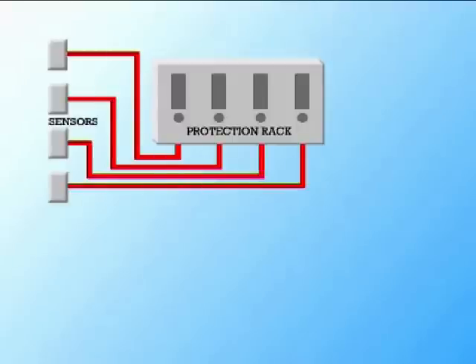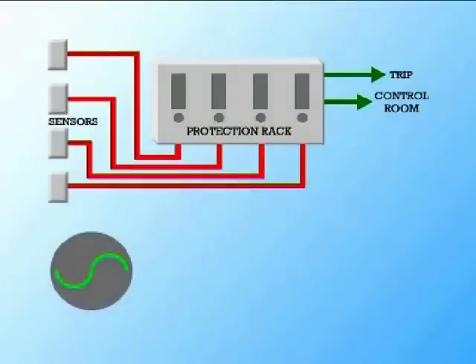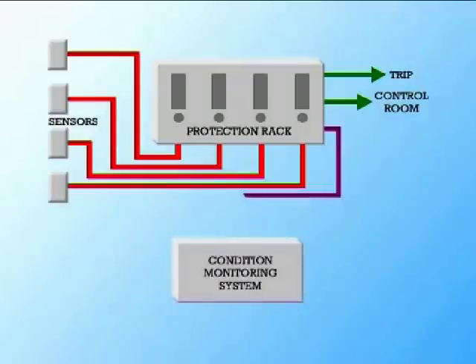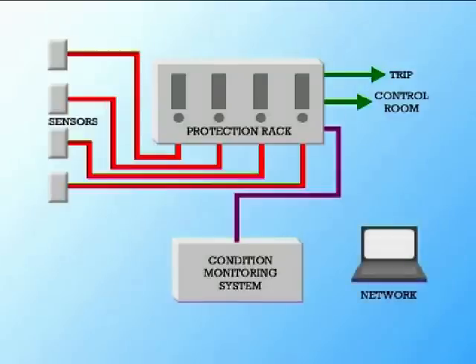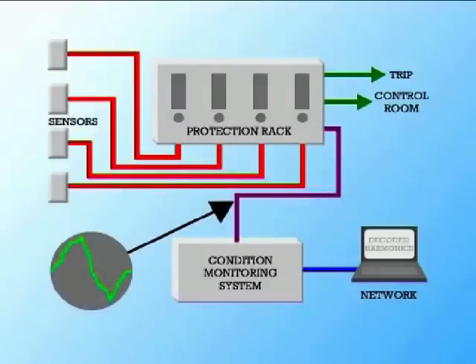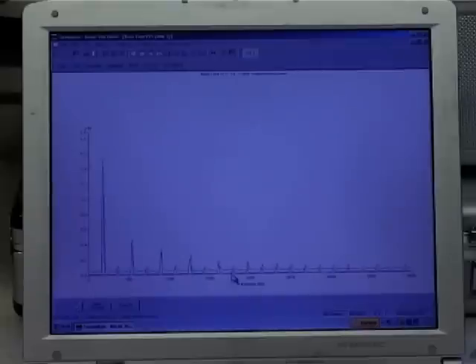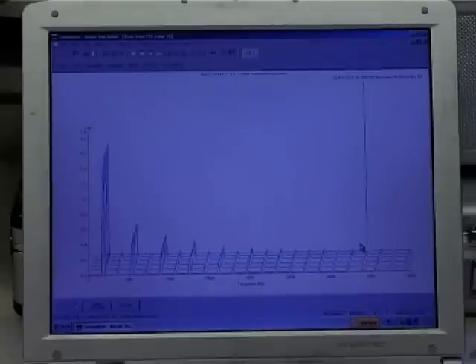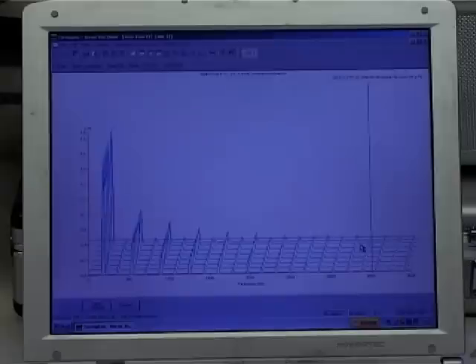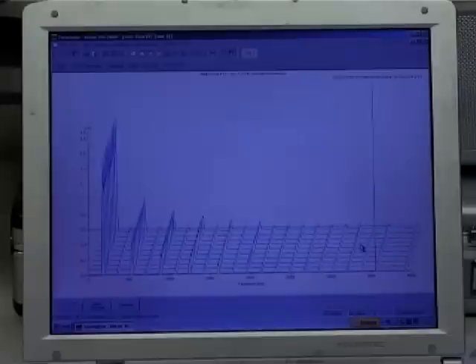Historically, vibration transducers have been calibrated at one frequency, such as 50 or 60 Hz. This used to be perfectly adequate because it was the predominant vibration frequency of interest. With the advent of modern condition monitoring systems, the performance of the vibration transducers and their associated integration and filtering electronics is critical. Condition monitoring systems decode the overall signal level into individual harmonics, phase relative to the once per revolution marker, and also display the amplitude of any individual harmonic components, often up to frequencies as high as 10 kHz in the case of pump and gearbox monitoring.